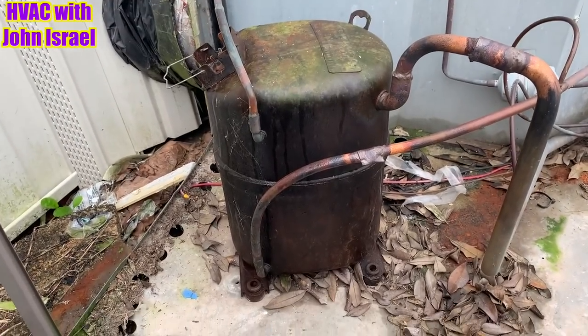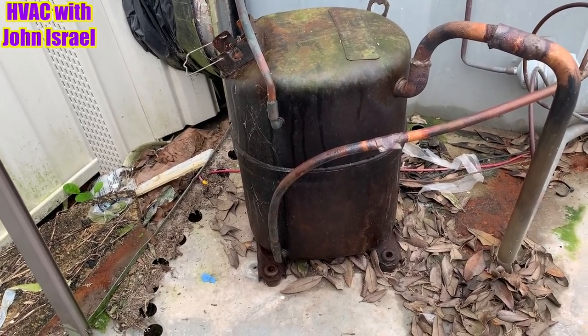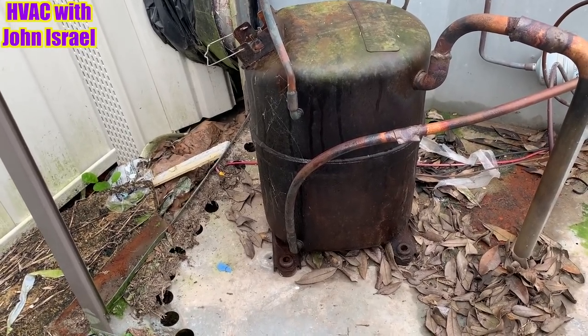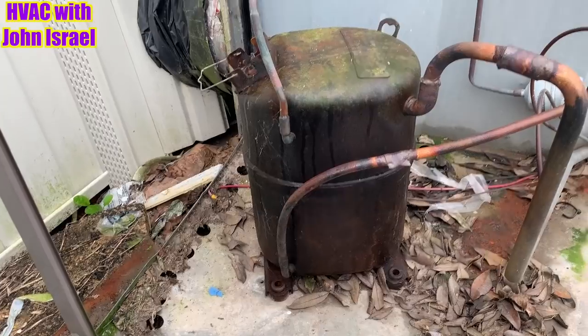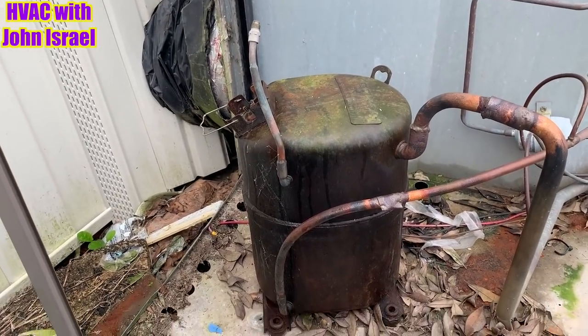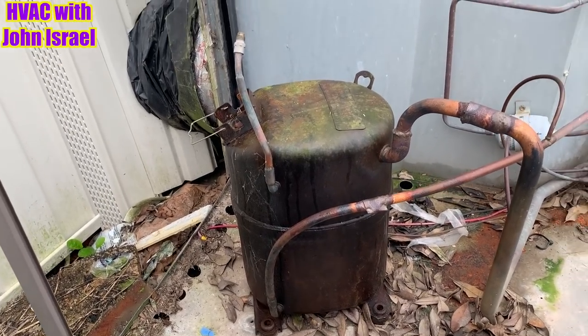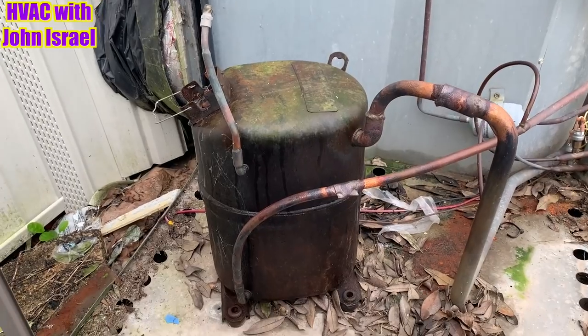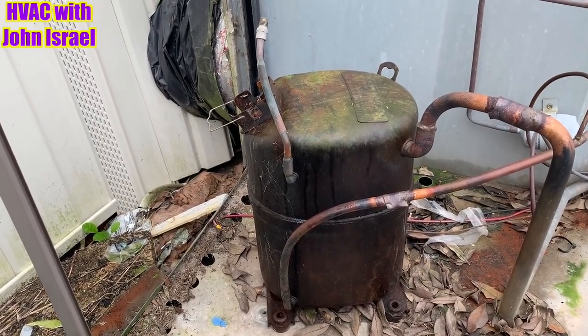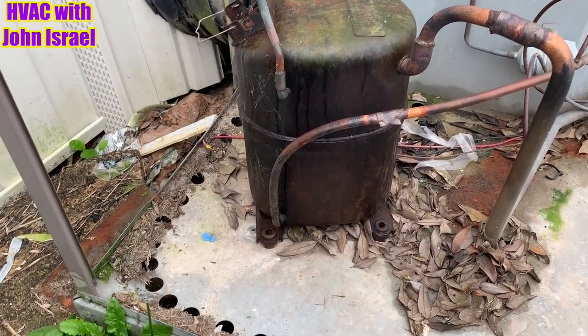I have a brand new Copeland Recip in the back of the truck. I know the other day I said I was going to put a Copeland Scroll in here — I just assumed this unit came from the factory with a scroll — but the York store said it came from the factory with a Recip. So they gave me a Copeland Recip compressor, 42,000 BTU. This is a four ton. They gave me a Copeland CR — C as in Charlie — CR42 compressor.